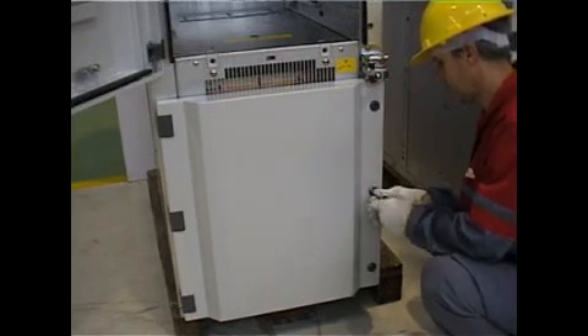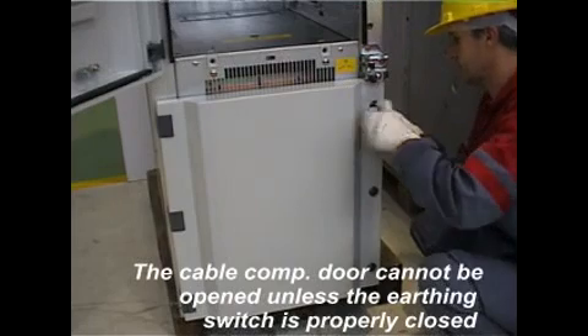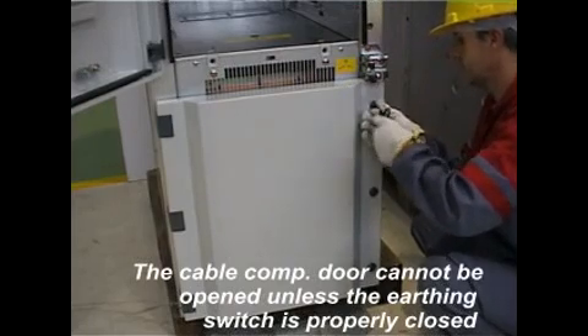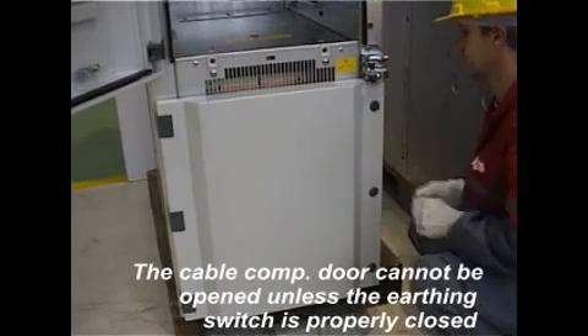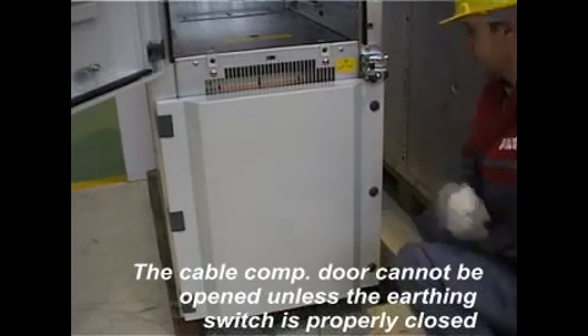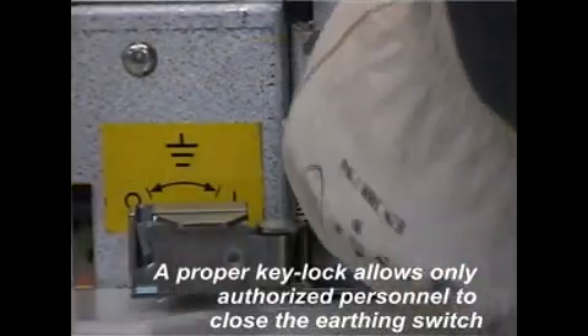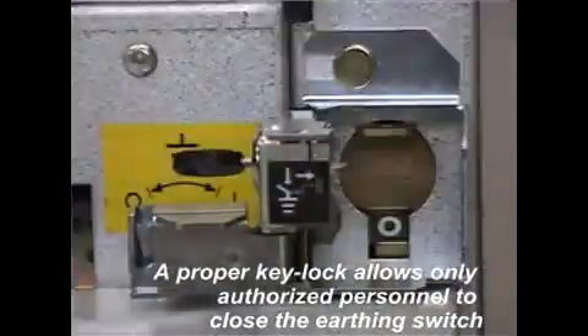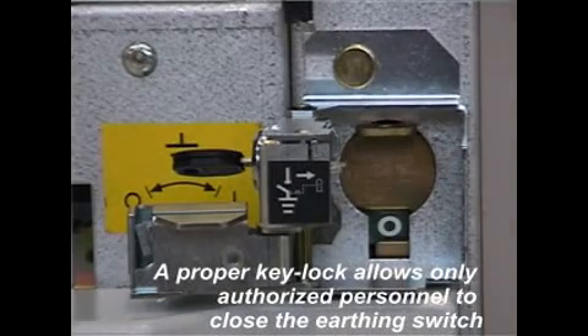We can go ahead and try to open the cable compartment in order to check the status of the terminals, but this operation is prevented by a proper interlock which requires the earthing switch to be in closed position. To earth the cable side, we insert the key to get access to the proper shaft, then we insert the lever and we operate the earthing switch.